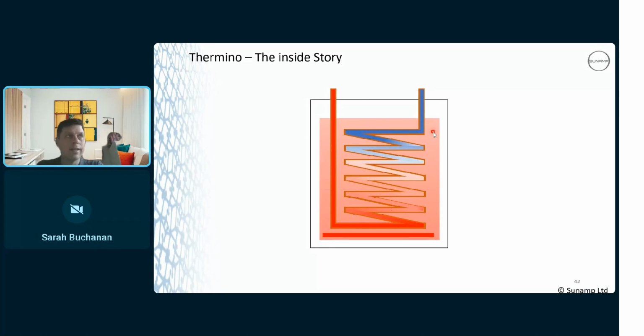I get a lot of jobs where customers have them set to 2 hours, then they call saying they're not getting enough hot water. They might get one shower but not 2 or 3 showers out of it, because they haven't got the timing cycle on long enough. Or even worse, customers without a timer just have a double pole isolating switch, and they treat it like an old school immersion switch, putting the power on for an hour then turning it off again. That's never going to work, because if you're only at half capacity, your preheat is only going to start partway. You'll still get hot water, but maybe not the full capacity for the customer's requirements. So it's important to manage the customer's expectations.